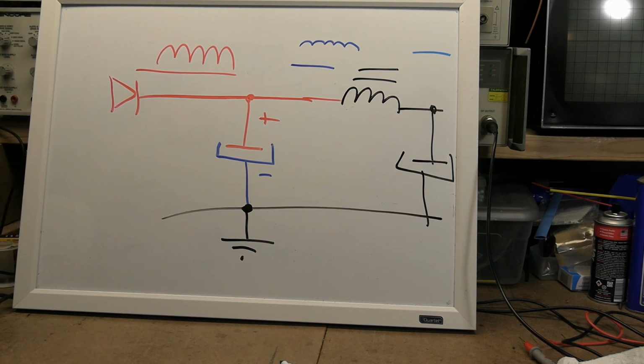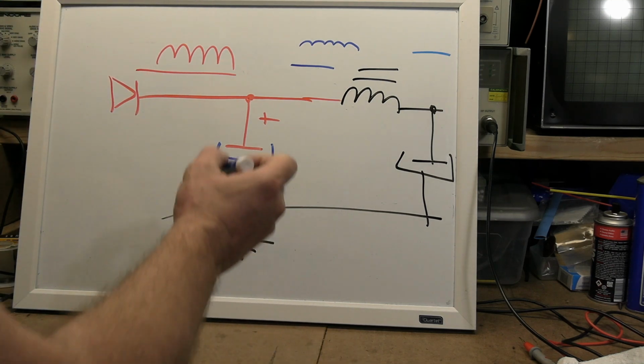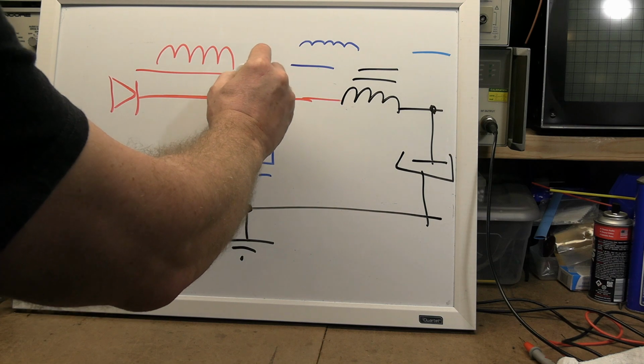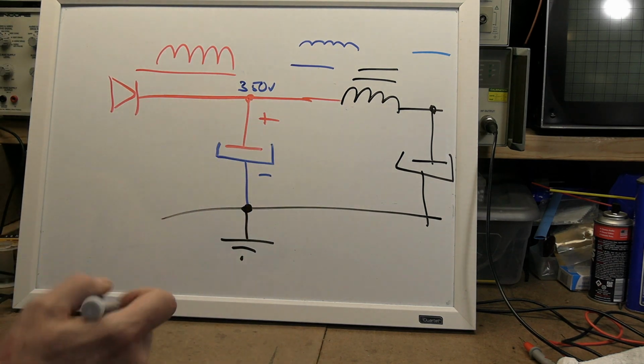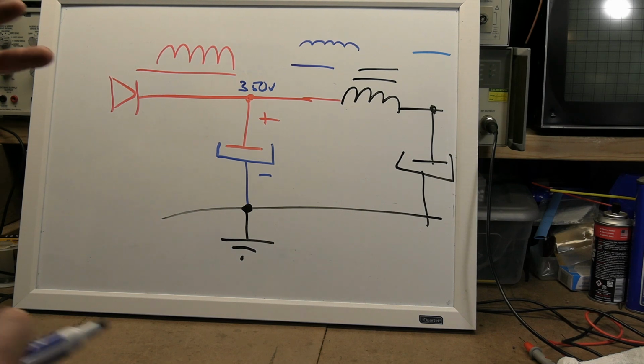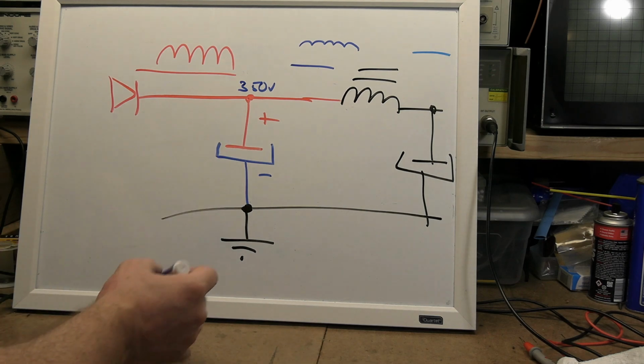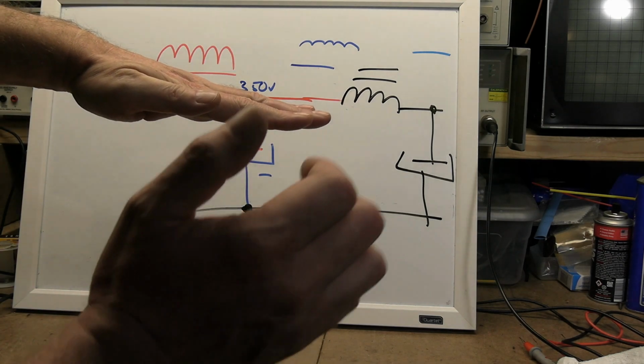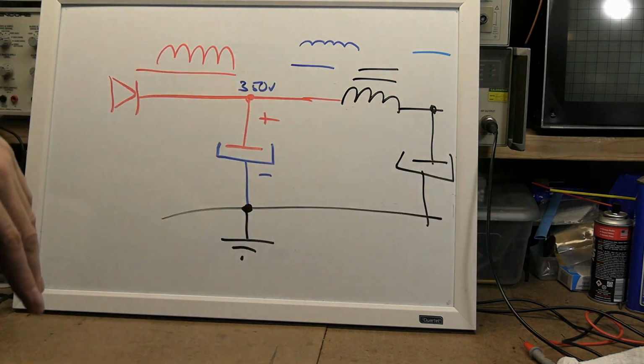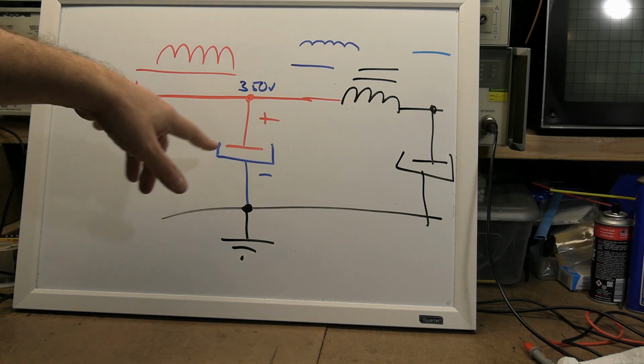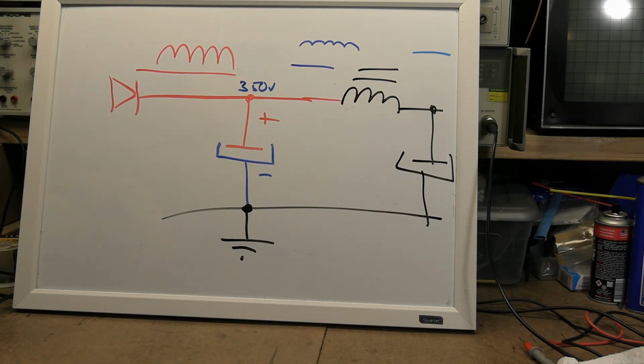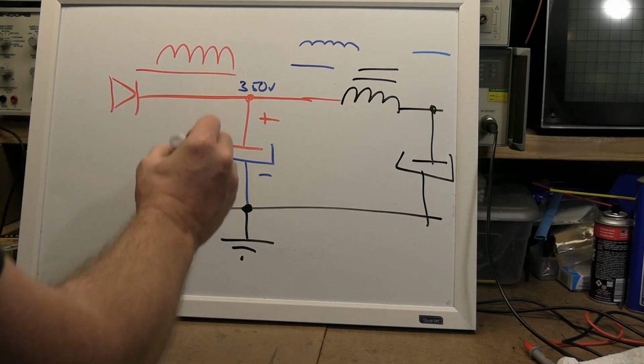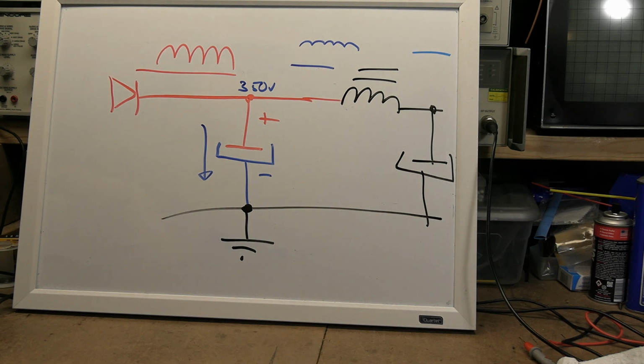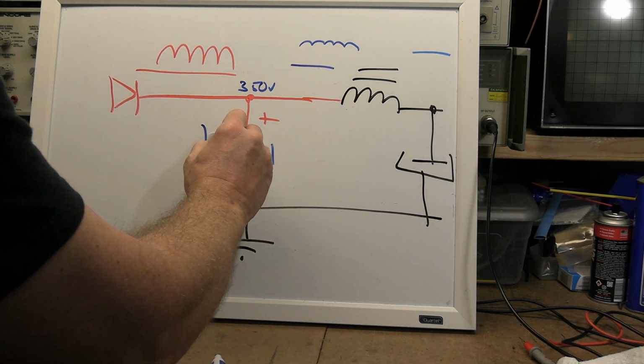However, if we were to just put full-on voltage into this, let's say it's a 350 volt cap, and we put a full 350 volts on this, and it's in bad shape, the chemicals have broken down, that insulating chemical layer has broken down, it's going to conduct. An ideal capacitor is a metal plate, and no current shall pass. A perfect insulator. Over time, even if you buy new caps, if they sit on the shelf for a few years, they're going to have leakage current. That's the term, meaning current is going to flow where it should not flow, because this insulating layer in here is deteriorated.